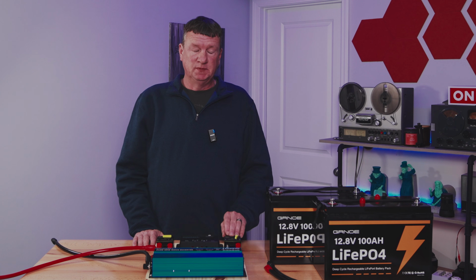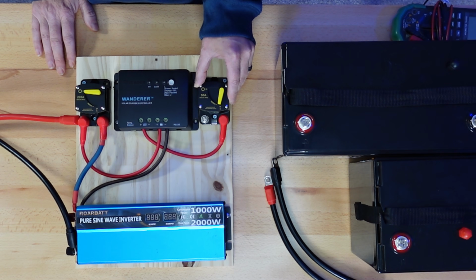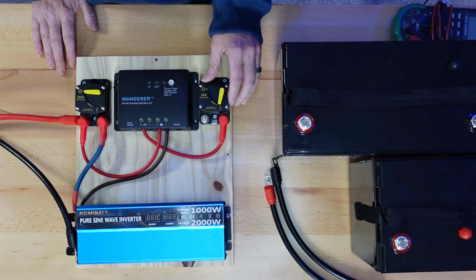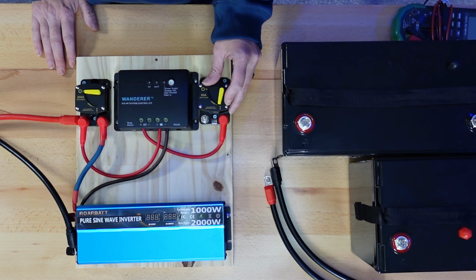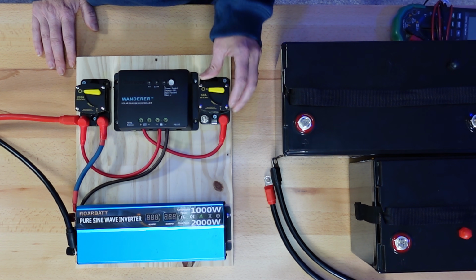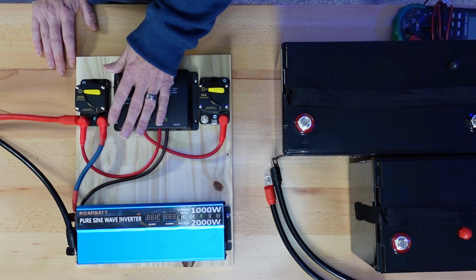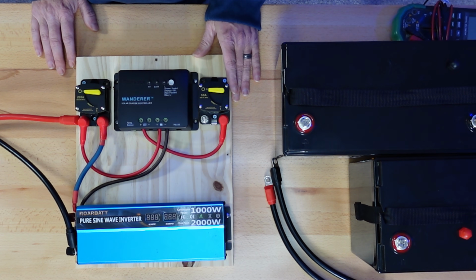We'll start with the input. On the input side, where the solar power is coming in, I decided to put a 50 amp circuit breaker. This serves two purposes: it gives me protection in case of a short, and also lets me easily disconnect power if I need to do maintenance on the system.